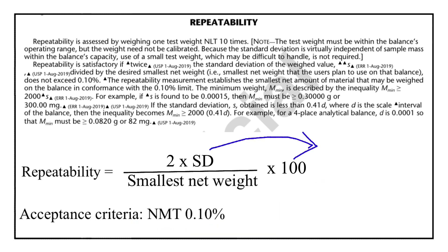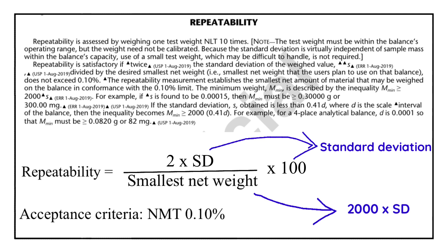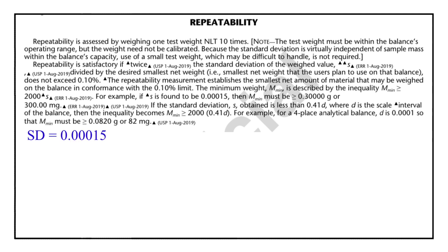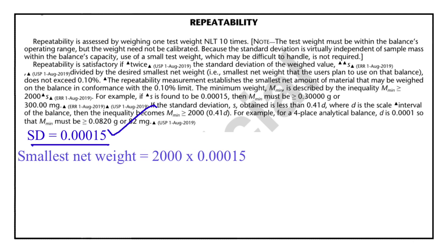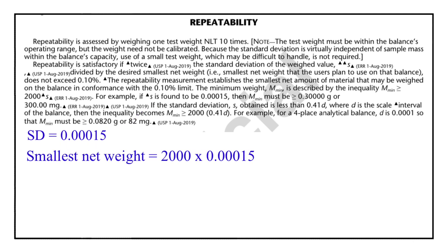In this formula, SD means standard deviation; this value can be taken from the weight print, and modern day balances automatically calculate the standard deviation value. Now comes the smallest net weight — this is calculated by the formula: smallest net weight = 2000 × standard deviation. Suppose standard deviation equals 0.00015, then the smallest net weight will be equal to 2000 × 0.00015, which equals 0.3 gram or 300 milligram.